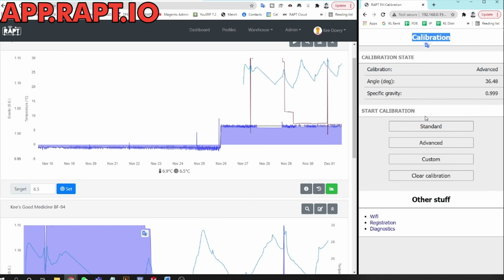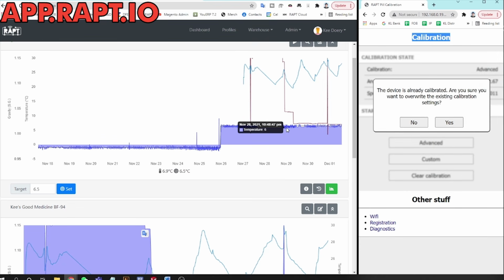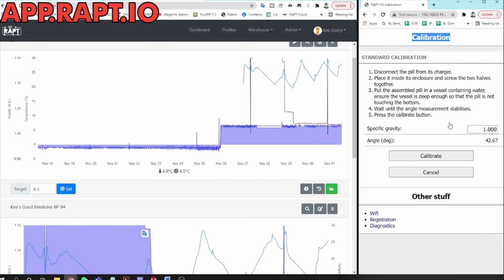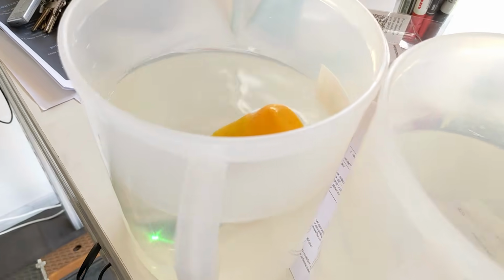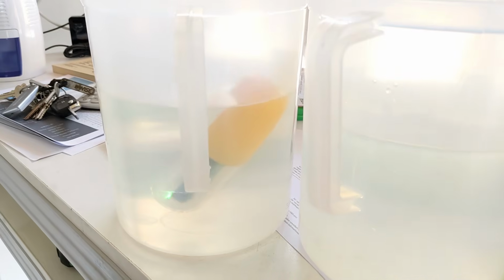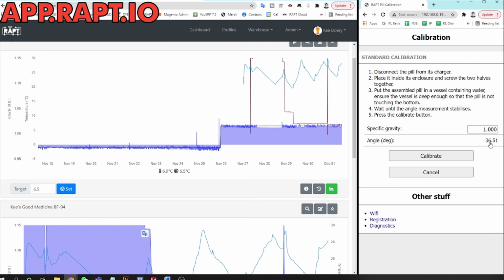Anyway, once I've done that, you can see in the calibration, there's standard, advanced, and custom calibration. So for most of you who just want general use and pretty good accuracy, the standard calibration is perfectly acceptable. So what I'm going to do is hit yes to standard calibration. Now what I have to do is drop the pill into a jug of water. I've got a jug of water on my desk, which the pill's sitting in right now. I'm going to keep an eye on this, and you can see that it now has this reading here, the 34, 36. It's still moving around a little bit, like it's bobbing up and down in the water. Normally what you would do is wait for this number to stabilize somewhat.